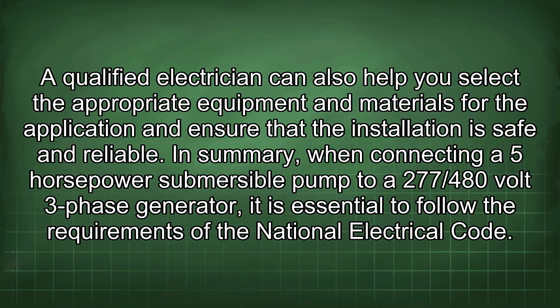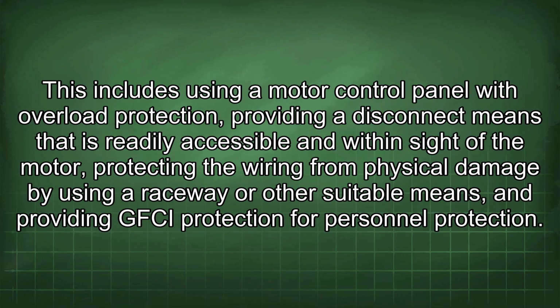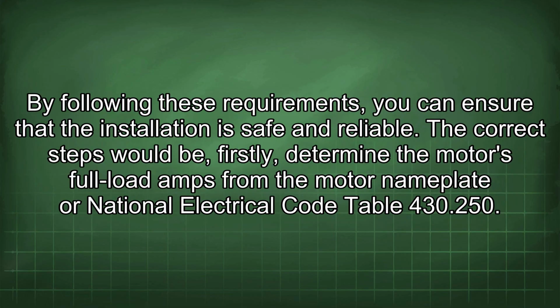In summary, when connecting a 5 horsepower submersible pump to a 277/480 volt 3-phase generator, it is essential to follow the requirements of the National Electrical Code. This includes using a motor control panel with overload protection, providing a disconnect means that is readily accessible and within sight of the motor, protecting the wiring from physical damage by using a raceway or other suitable means, and providing GFCI protection for personnel protection. By following these requirements, you can ensure that the installation is safe and reliable.